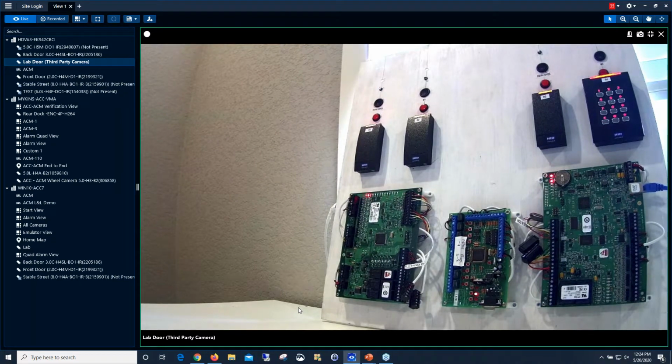So we know it works. The door is forced open. Now we need to test, you know, somebody presents their card, opens the door, and just forgets to close it. Is it still going to disable the other door? So let's check and make sure.